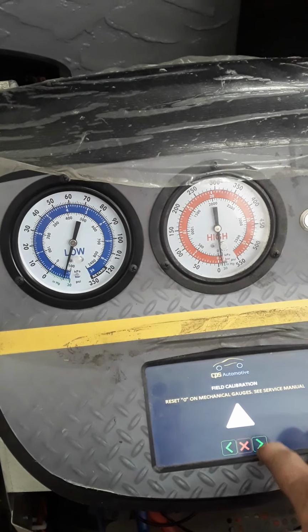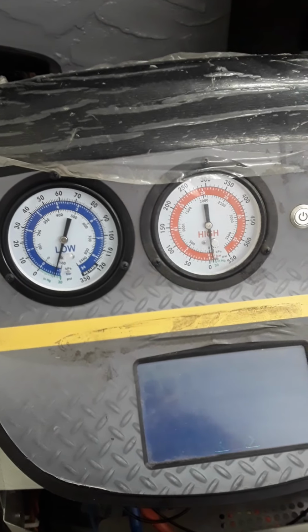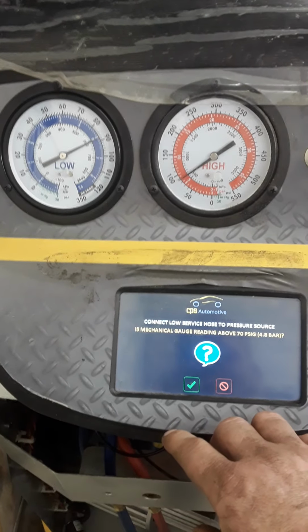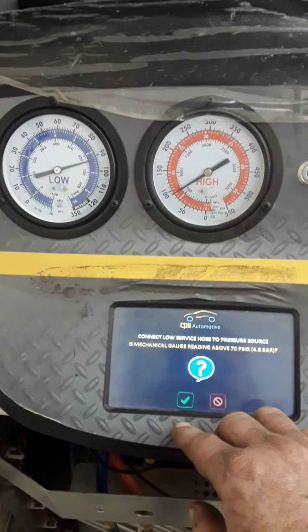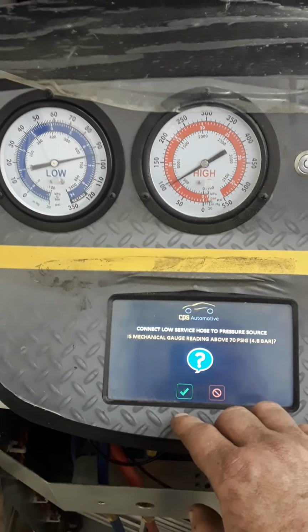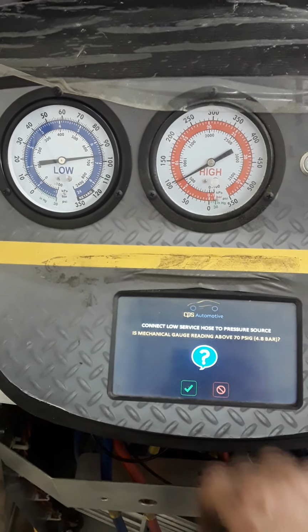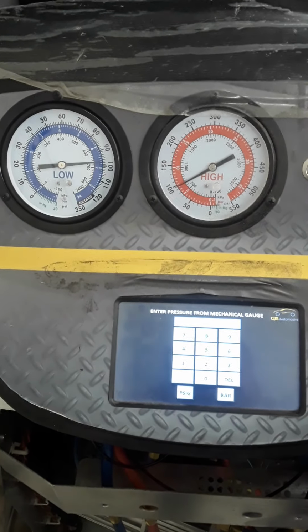Well, yeah, what you're supposed to do when you get to that screen is break loose the low side manifold hose going up under the bottom of the machine. When you crack it loose, it should go to 0. If it doesn't, you're supposed to take a small pocket screwdriver, remove the plastic plug out of the face lens of the gauge, and make it read 0 without the hose on it. Right. That's all you're supposed to do.